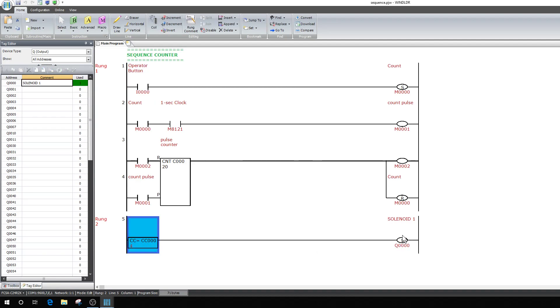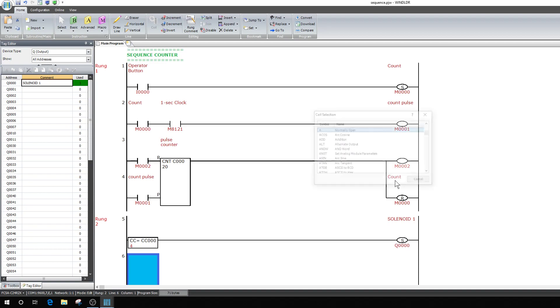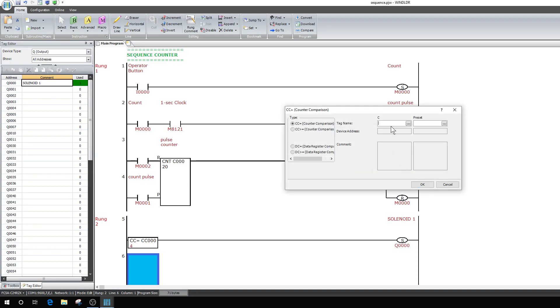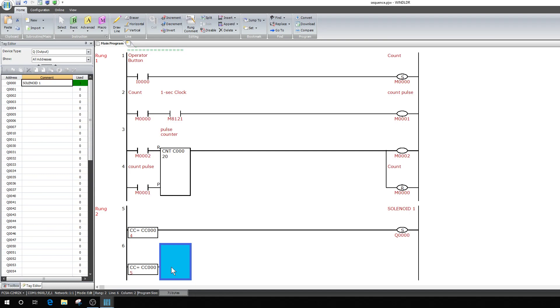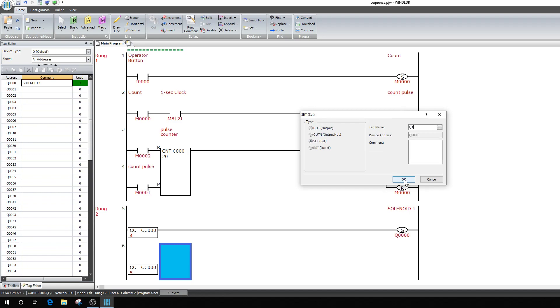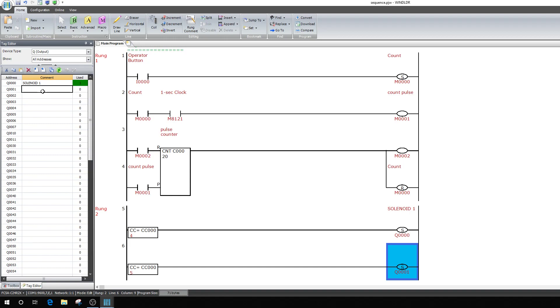Now I want my second solenoid to come up and retract. I'll add another counter comparison, same counter C0, and I want it to operate one second after the first — so at 5 seconds. This will SET output Q1. In the tag editor, Q1 would be labeled with the name of your device — like 'Retract Arm' or 'Raise Arm' — that helps you remember what you're programming. So: at 4 seconds this arm goes up, at 5 seconds this arm retracts.